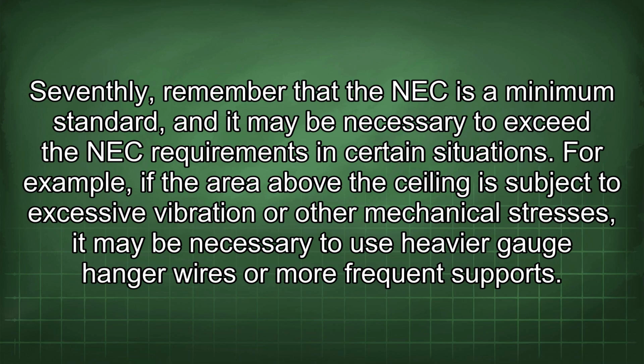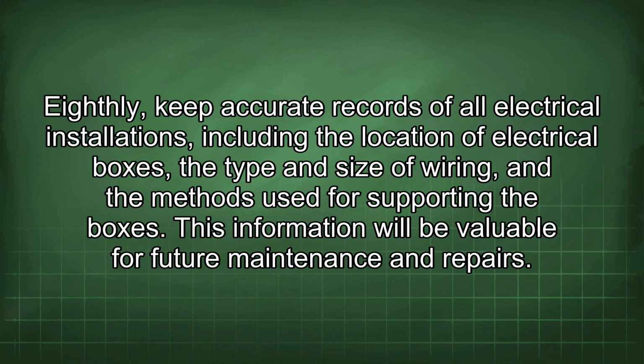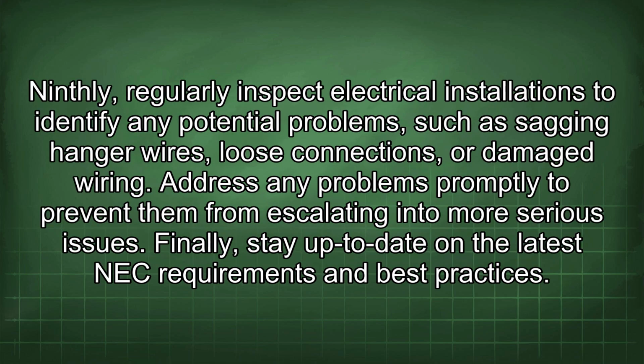Seventhly, remember that the NEC is a minimum standard, and it may be necessary to exceed the NEC requirements in certain situations. For example, if the area above the ceiling is subject to excessive vibration or other mechanical stresses, it may be necessary to use heavier gauge hanger wires or more frequent supports. Eighthly, keep accurate records of all electrical installations, including the location of electrical boxes, the type and size of wiring, and the methods used for supporting the boxes. This information will be valuable for future maintenance and repairs. Ninthly, regularly inspect electrical installations to identify any potential problems, such as sagging hanger wires, loose connections, or damaged wiring. Address any problems promptly to prevent them from escalating into more serious issues.